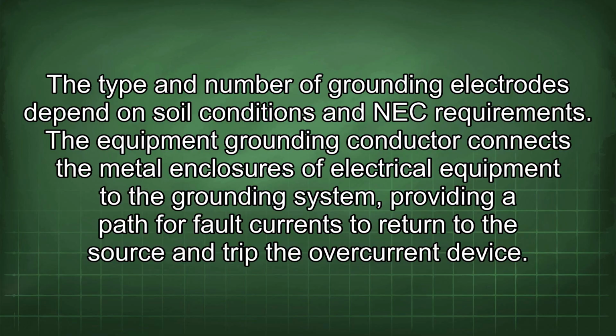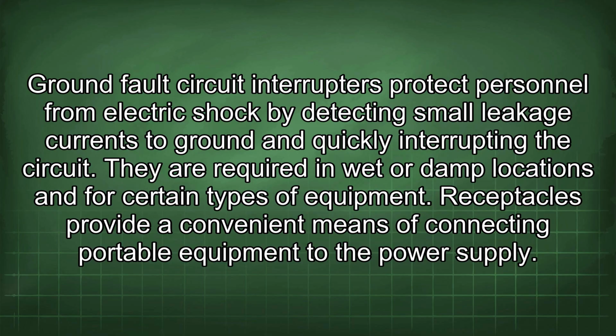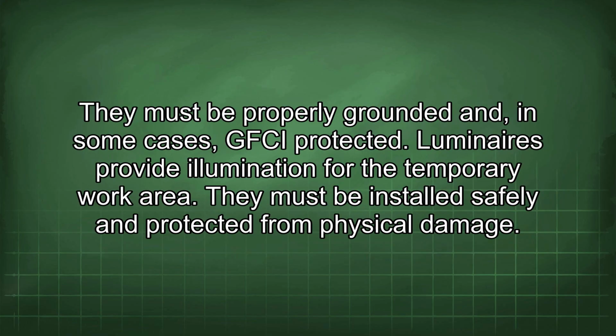The equipment grounding conductor connects the metal enclosures of electrical equipment to the grounding system, providing a path for fault currents to return to the source and trip the overcurrent device. Ground fault circuit interrupters protect personnel from electric shock by detecting small leakage currents to ground and quickly interrupting the circuit. They are required in wet or damp locations and for certain types of equipment. Receptacles provide a convenient means of connecting portable equipment to the power supply. They must be properly grounded and, in some cases, GFCI protected.